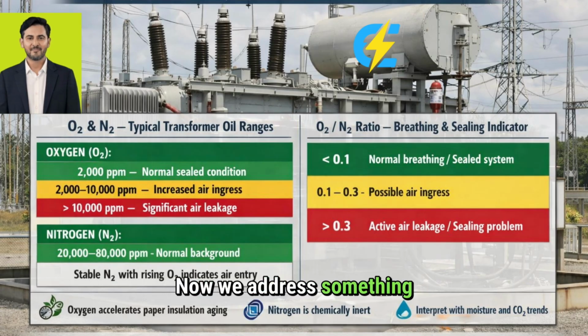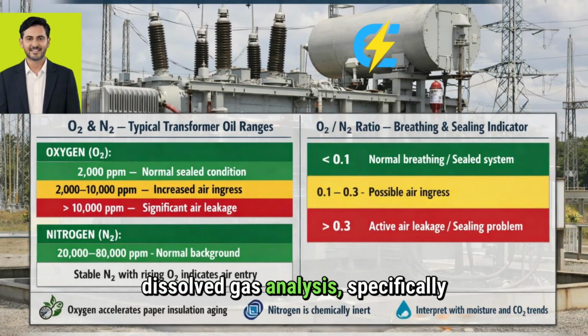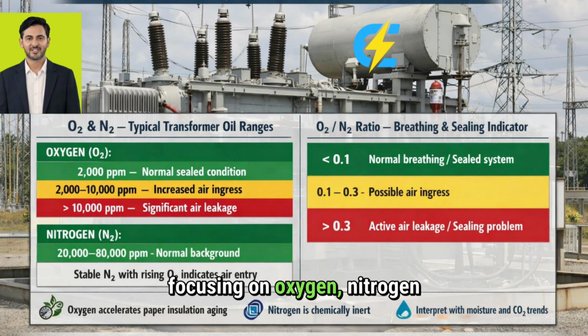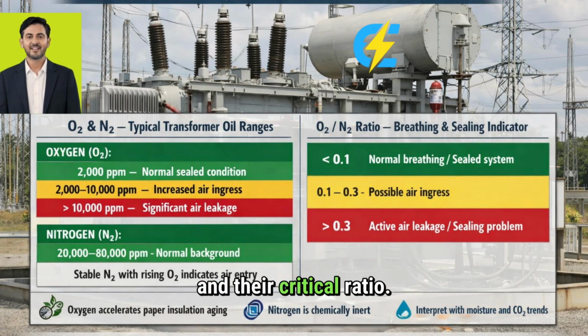Now we address something silent, slow, and extremely dangerous if ignored. Air ingress. This episode tells you whether your transformer is truly sealed and protected. We're diving deep into the technical aspects of dissolved gas analysis, specifically focusing on oxygen, nitrogen, and their critical ratio. As an experienced engineer, I'll walk you through why these gases matter more than you think they do.